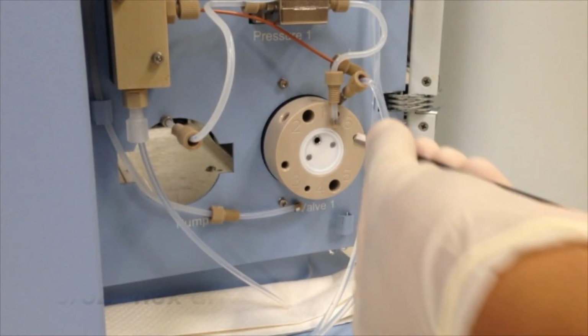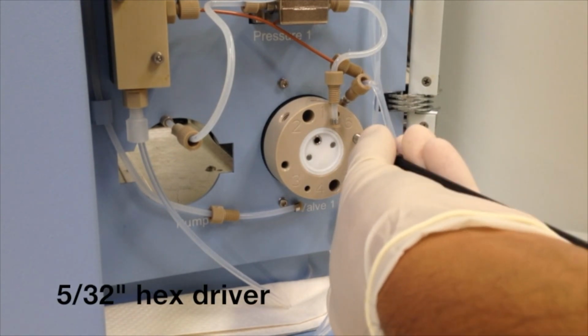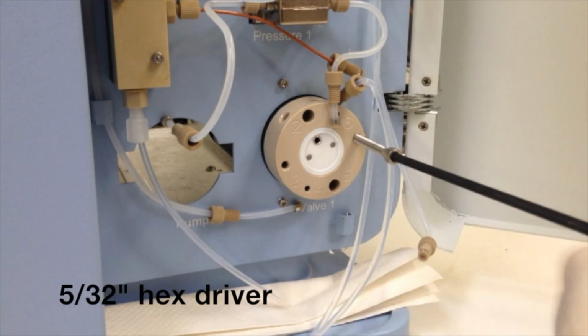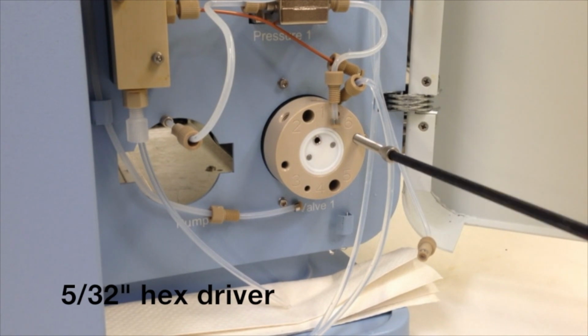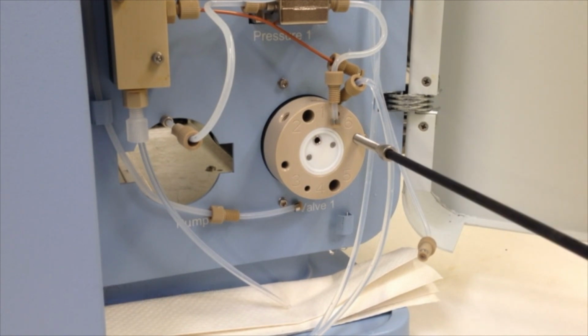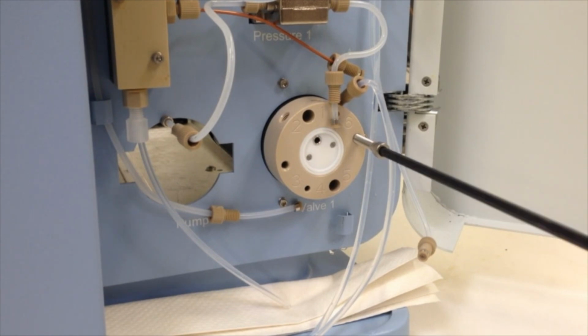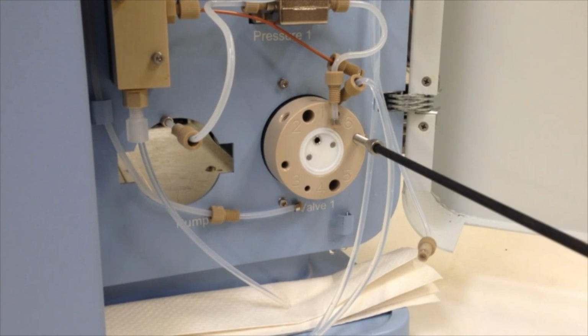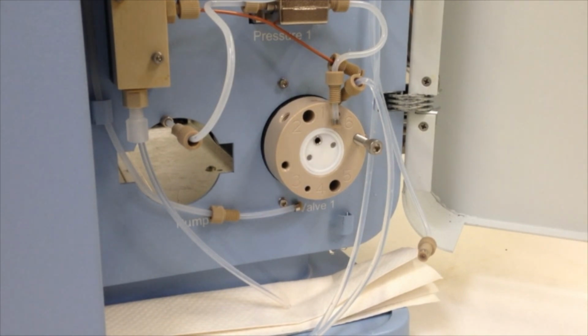If there was a major valve leak and you cannot remove the valve face due to crystal buildup, install jack screws to gently remove the valve face. Use a 5/32" hex driver to screw in the jack screws. Tighten each jack screw with equal turns until the valve face comes off.